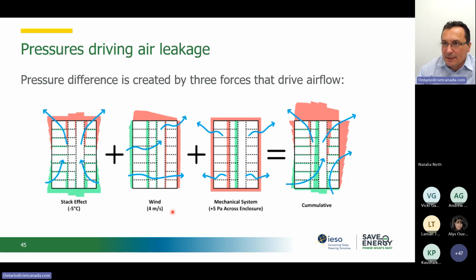We also see this infiltration created by the pressure caused by the wind. So we see higher pressure on the windward side of the building. And in some cases, we may see poorly balanced systems creating this imbalance of the pressure from inside to outside. So if we exhaust more air than we introduce into the building with the makeup air units, we unbalance the system as well. And again, I wouldn't say all buildings, but several multi-unit residential buildings, high-rise buildings, will see this type of effect in the corridors. The corridors in multi-unit residential buildings are meant to be pressurized to prevent exhaust air coming from the units, let's say cooking or bathroom, from coming into the corridors. But sometimes you can feel that because the balancing is not operating properly.